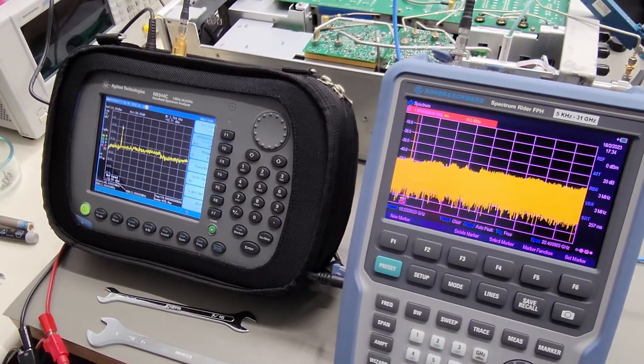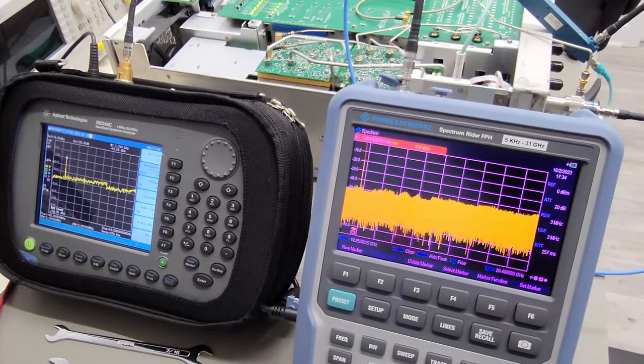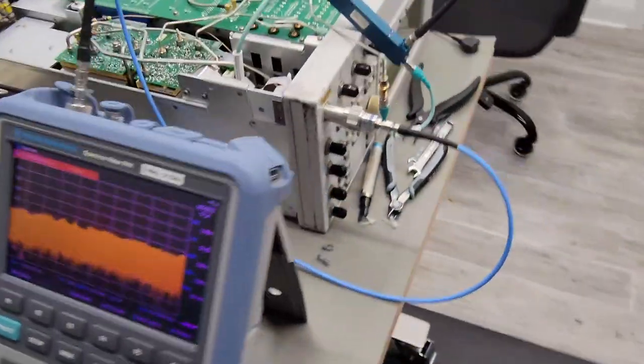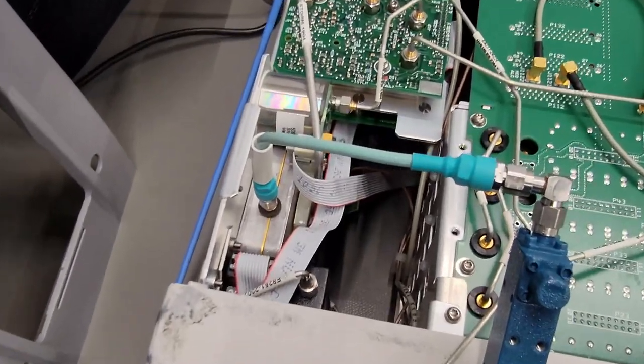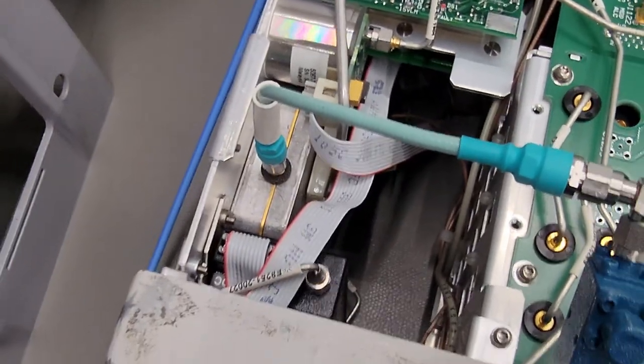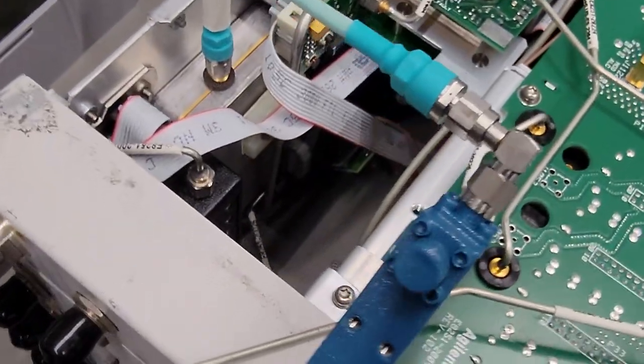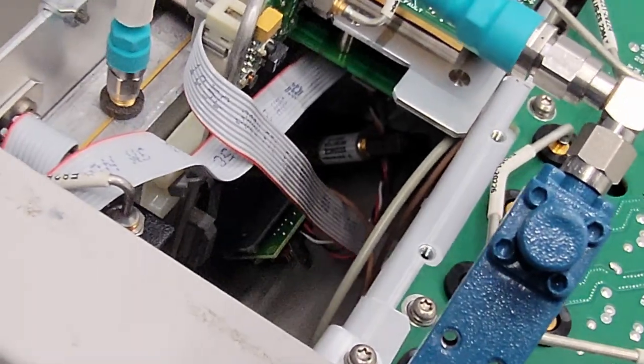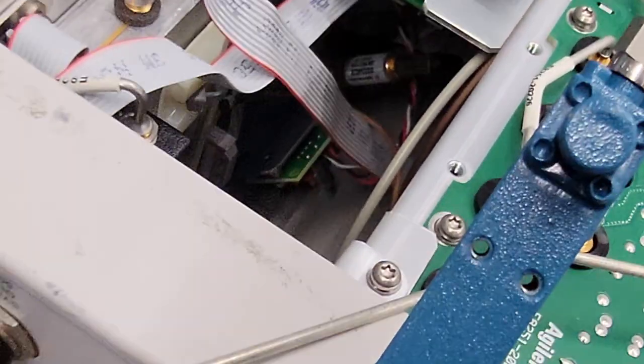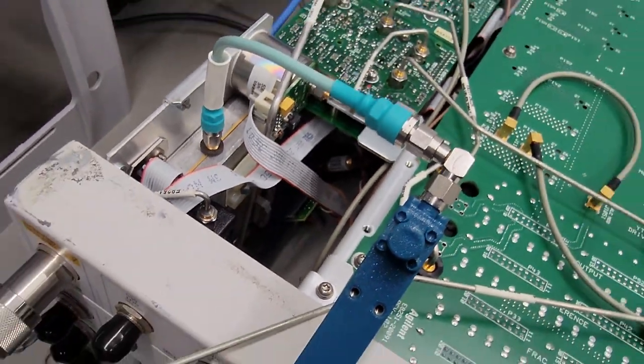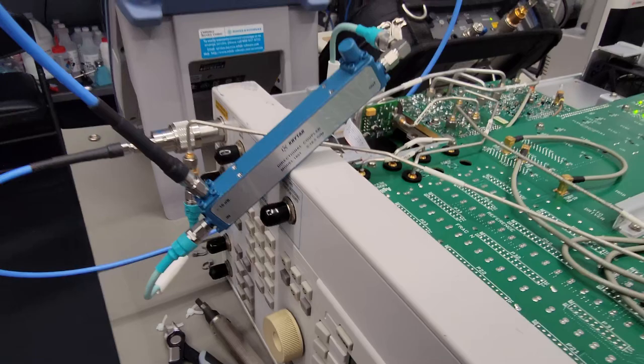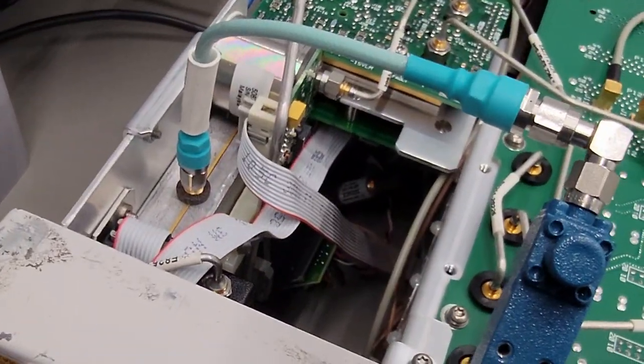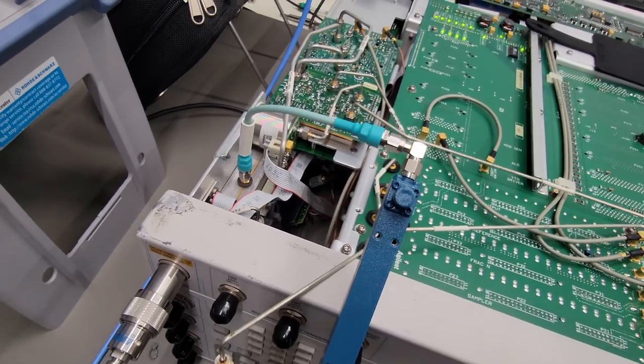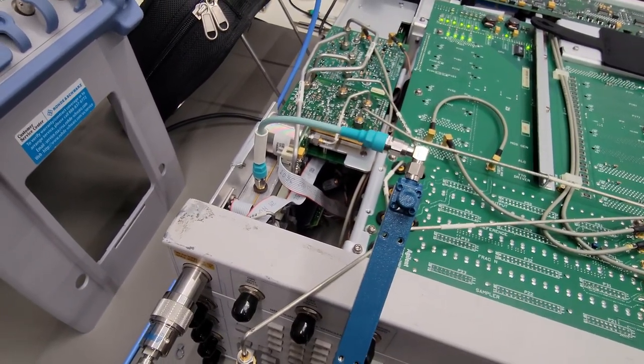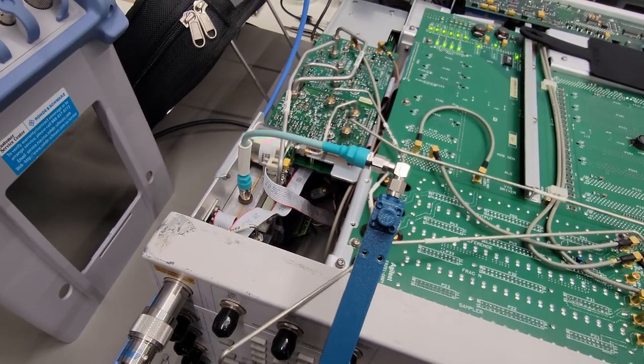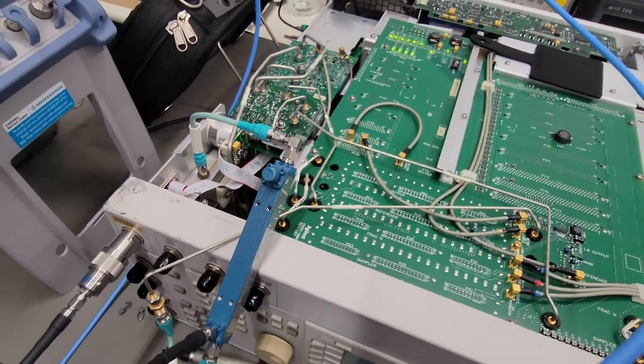And I would have initially suspected one of the couplers or detectors, because there are actually two. For the low band, the coupler and detector are one module that's encased there. But if you remember previously, you can kind of see the high band detector diode assembly there in the detector bias board. For the high band, there is another directional coupler that looks very much like this, of course, inside the instrument with a detector on the coupled port. And that's what reports the instrument's output power level to the ALC above a few gigahertz and provides amplitude leveling that way for the output.